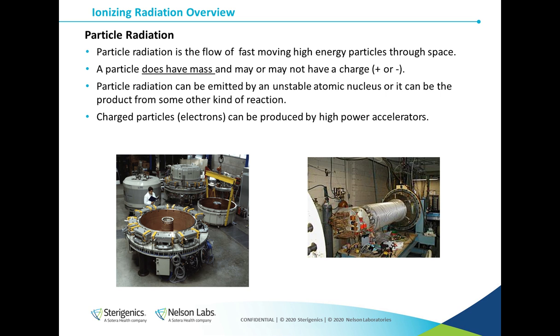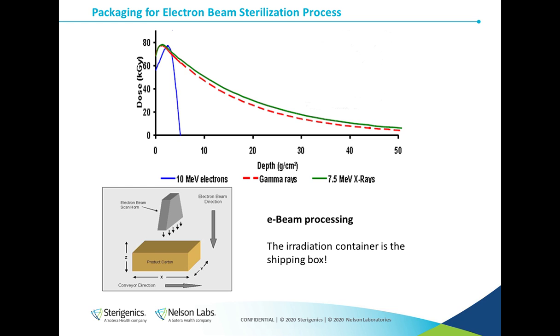The pictures at the bottom of this slide depict the inside of an IBA Rhodotron accelerator on the left-hand side and a type of linear accelerator on the right-hand side. In both cases, there is a vacuum chamber wherein the particles are accelerated through some means to relativistic speeds and energies in order to be used for the electron beam irradiation process.